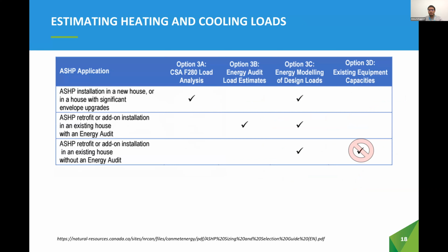For houses that have completed energy efficiency evaluations, particularly those which have the EnerGuide rating system evaluation, design loads can be estimated based on the information contained in the audit report. Also, energy modeling software such as HOT2000 can be used to estimate design heating and cooling loads based on the construction details of the building envelope. And lastly, I'll note that while there is no precise way of estimating loads from installed equipment capacities, this approach should only be used as a very, very last resort.